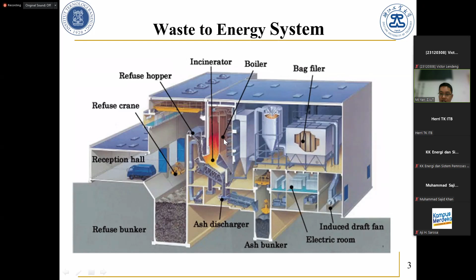And this is the thermodynamics of WTE. So the incinerator produces steam in the boiler and drives the steam turbine. For the coal power plant, usually we will have a reheater, but for WTE, the reheater is not normal, because the pressure - even the initial or fresh steam - the temperature and pressure are not high enough. So after working in the steam turbine, the pressure is not high enough, so usually it's only a high pressure steam turbine at a low temperature, not a reheater or regenerator.